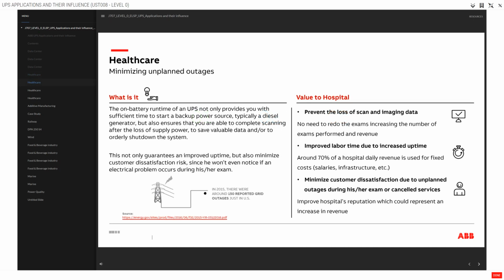Minimizing unplanned outages. The on-battery runtime of a UPS not only provides you with sufficient time to start a backup power source, typically a diesel generator, but also ensures that you are able to complete scanning after the loss of supply power, to save valuable data and/or to orderly shut down the system. This not only guarantees improved uptime, but also minimizes customer dissatisfaction risk, since he won't even notice if an electrical problem occurs during his/her exam.